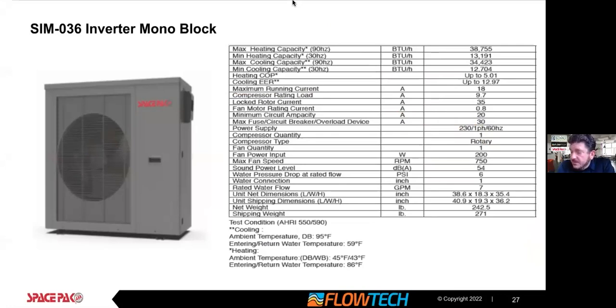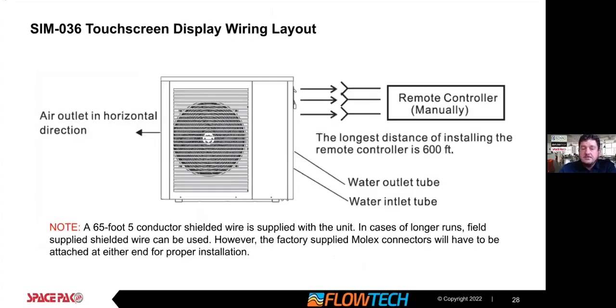So on the 3-ton, the unit itself is 13 feet of head at 7 gallons a minute. The larger unit is even more. So one of the common things that we're seeing a lot is undersized circulators on these units. So pay special attention to understand this pressure drop through the unit. The sizing of the units has a very similar footprint. This is a 38 by 18 by 35, and the 5-ton unit is taller, but the footprint stays the same.